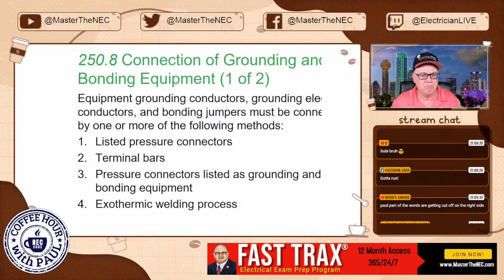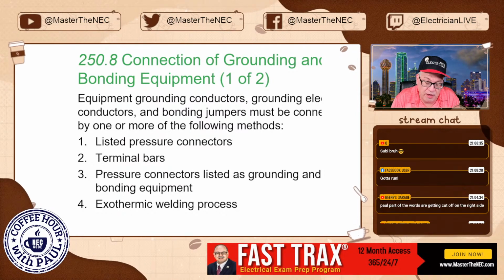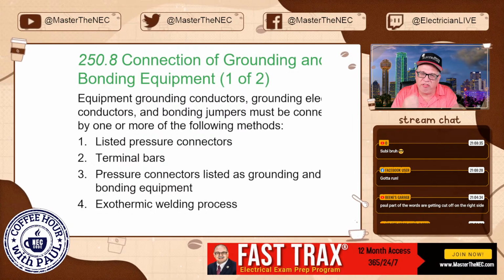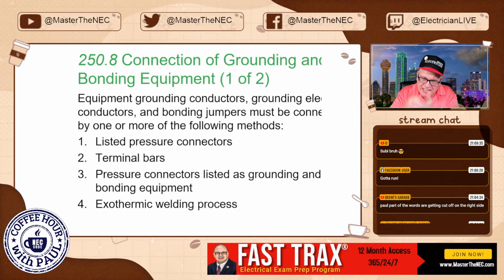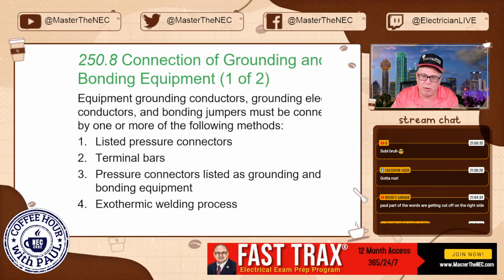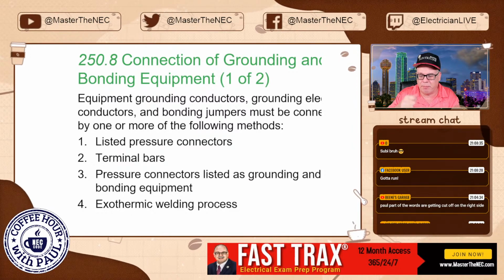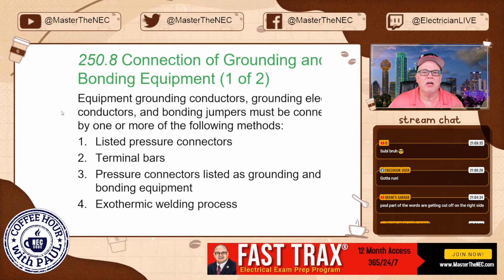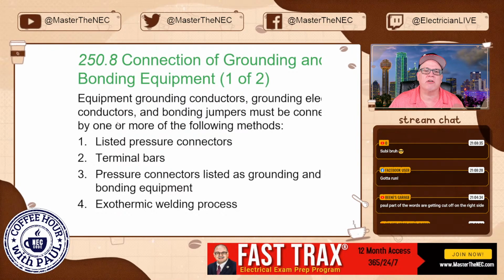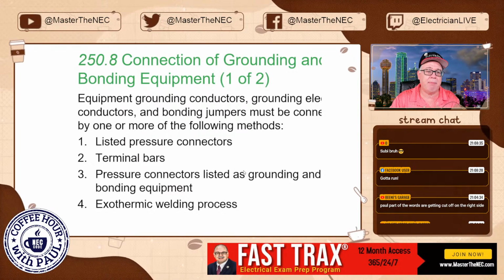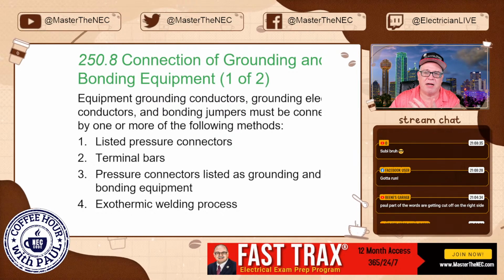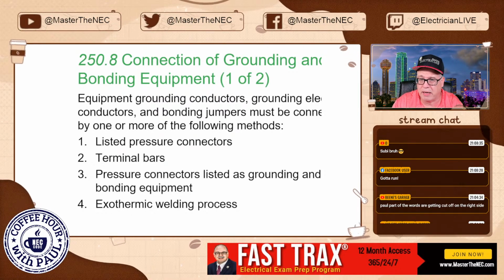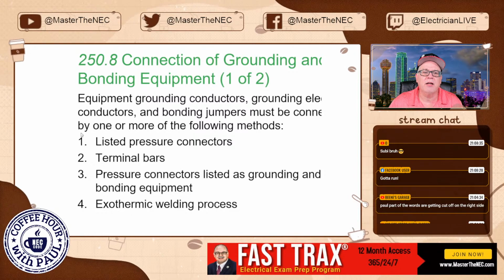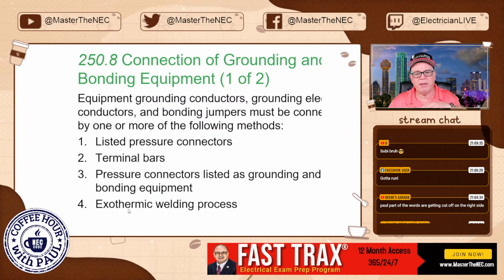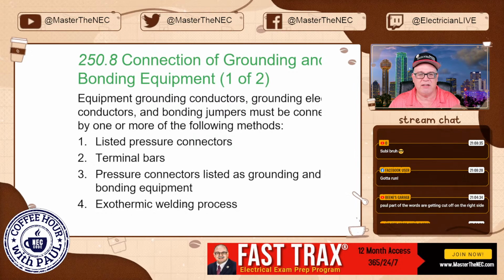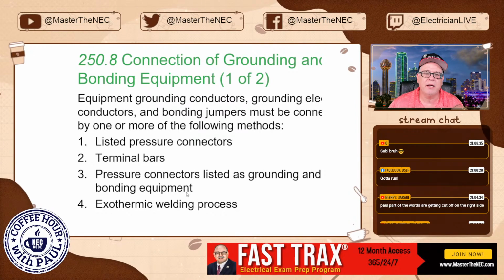250.8. One of my favorite areas in 250 because it's where the rubber meets the road. It's where I'm making those connections to grounding electrode conductors, equipment grounding conductors, system bonding jumpers, the actual connections. It says equipment grounding conductors, grounding electrode conductors, bonding jumpers, whether it's main bonding jumpers, system bonding jumpers, supply side bonding jumpers, all of those glorious bonding jumpers must be connected by one or more. So you don't have to just pick one.